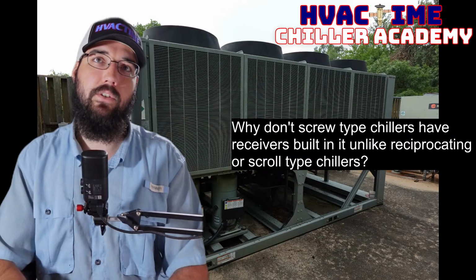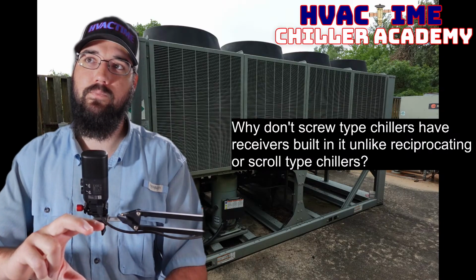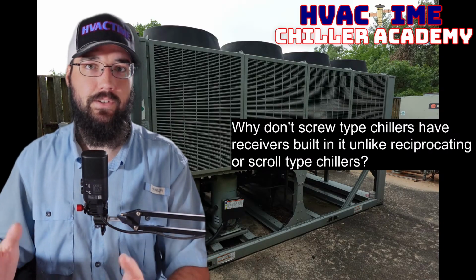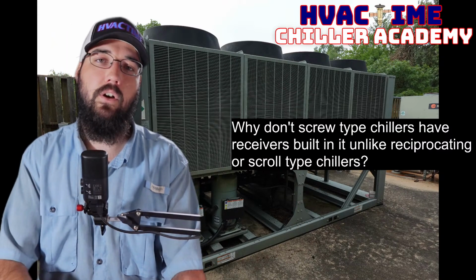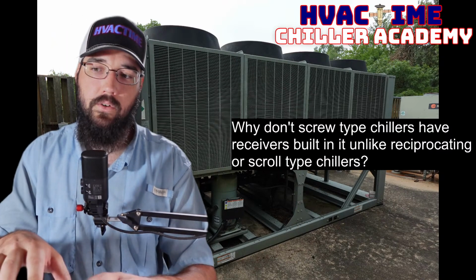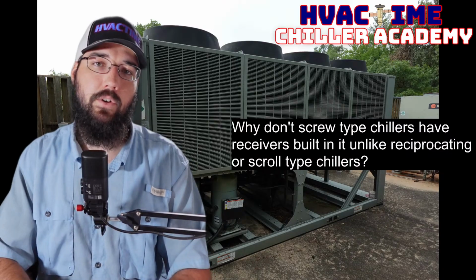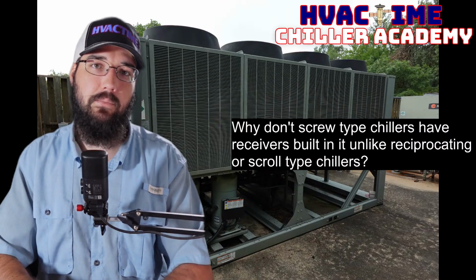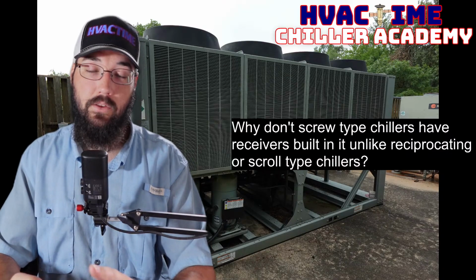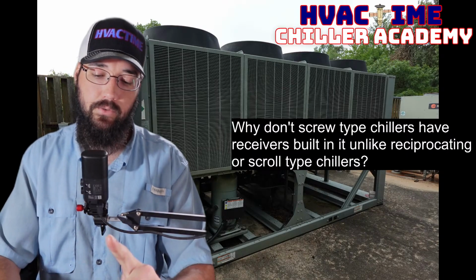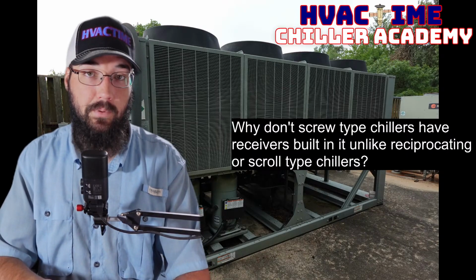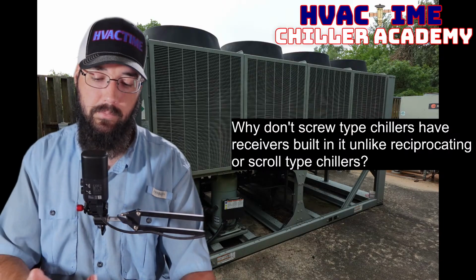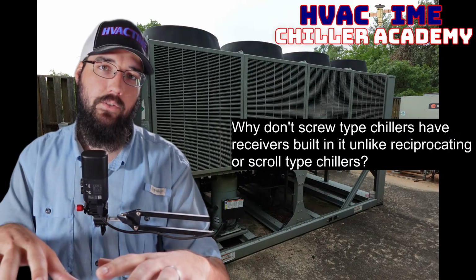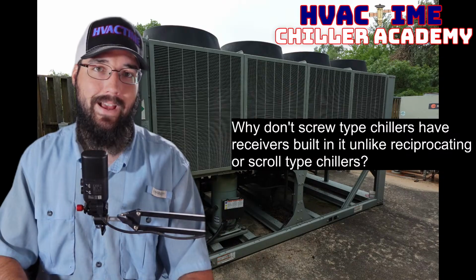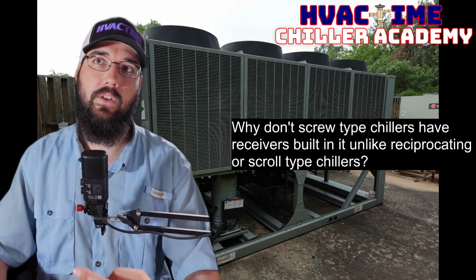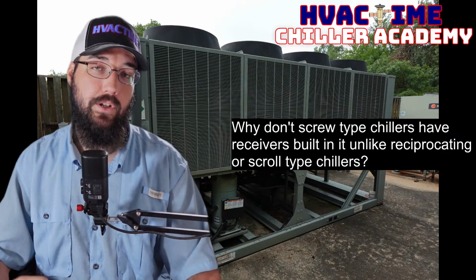We also have the ability to stack the refrigerant sufficiently. So when we are in a lower load scenario, one, we are heavily unloading the compressors. We have the ability with these types of machines, whether it be through the slide valve on the screw compressor, whether it be a variable speed if we have that, or both in some cases, to reduce the compressor capacity itself, which reduces the flow through the machine on its own.